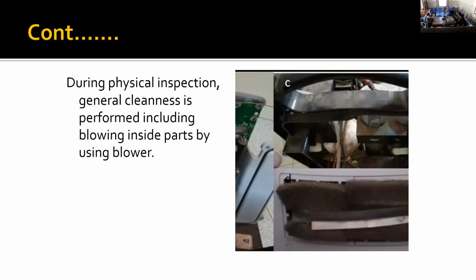So during physical inspection, general cleaning is performed, including blowing the inside parts using a blower. So you can see now the inside part of the oxygen concentrator. You have to do blowing to remove all the dust, and you do this during the first part, which is physical inspection.